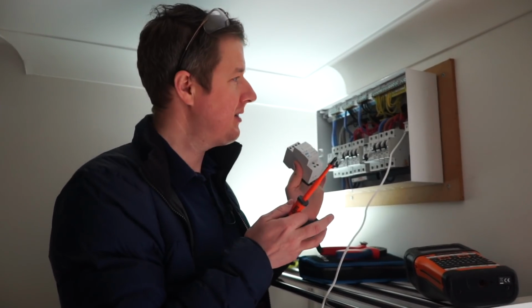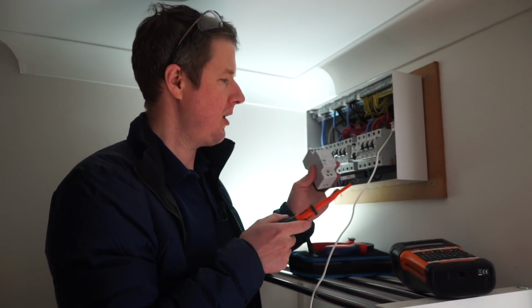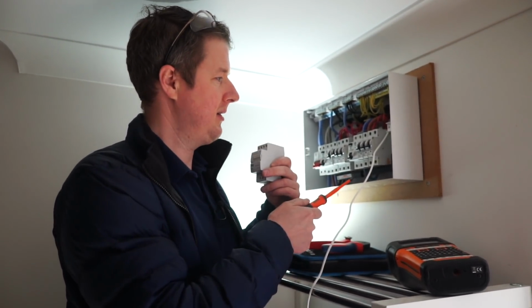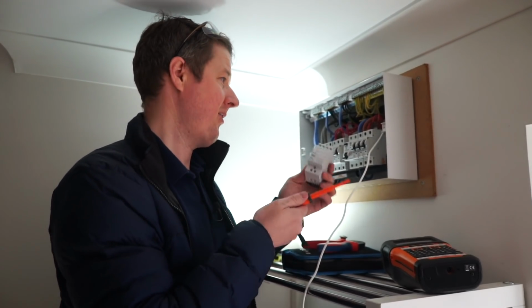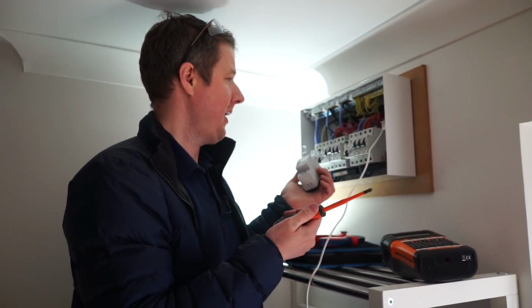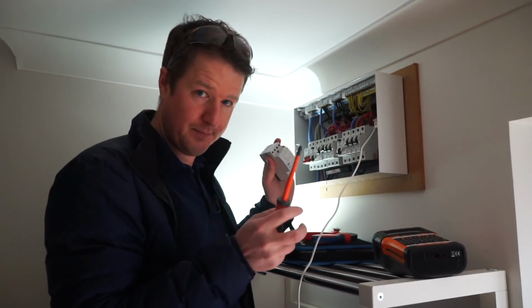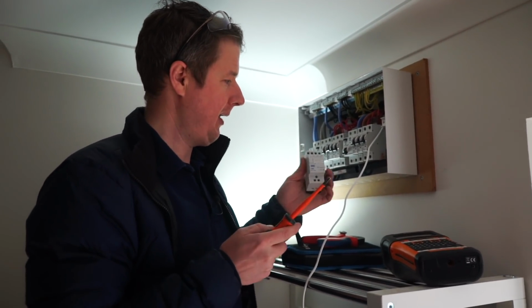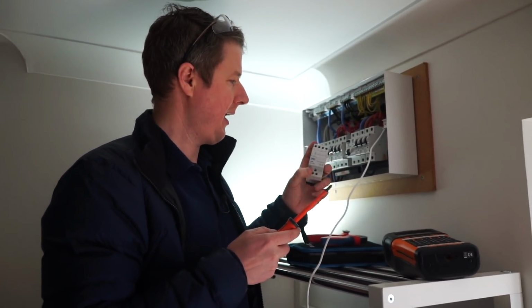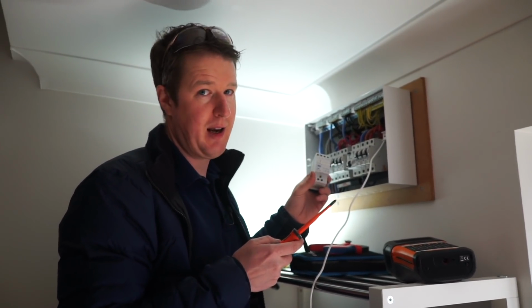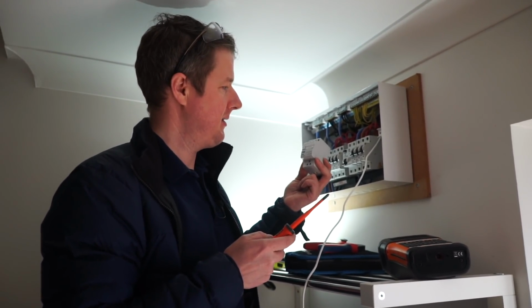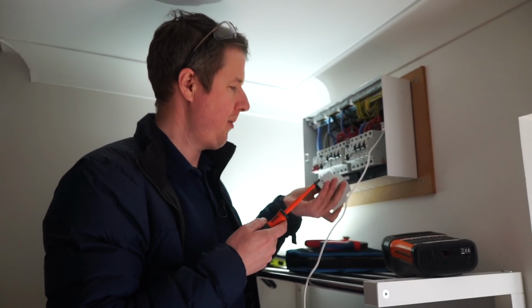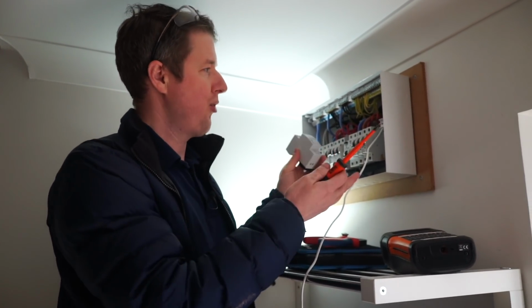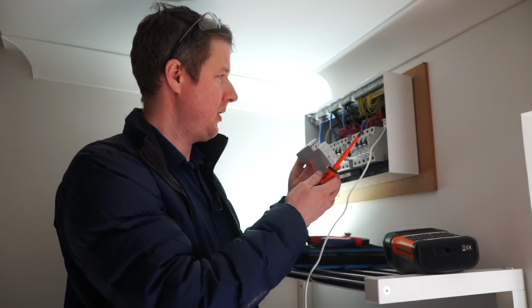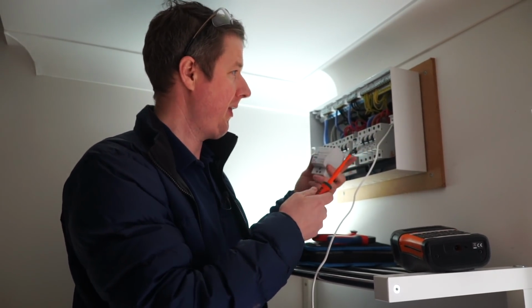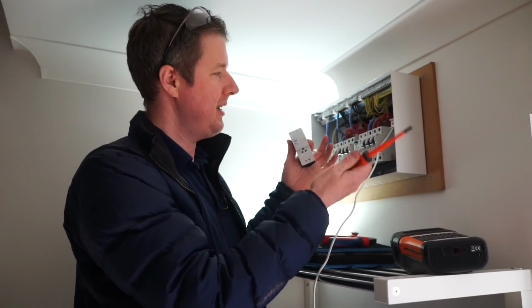Now, some of you might say you shouldn't install that because the BG transformer isn't type tested for an MK consumer unit, and yeah, I suppose technically you're right. But let's think about this - they all basically come out of the same factory anyway. This is safety tested by its own manufacturer and there's plenty of room in there. It's not like you're going to get a massive heat build up or anything like that - there's plenty of room for the heat to dissipate.